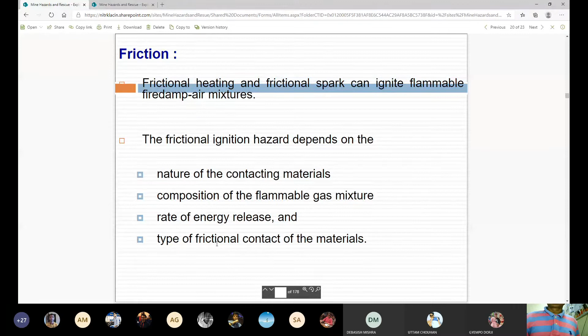So the frictional ignition hazard depends on four factors: the nature of contacting materials, which material is contacted with which material; the composition of the flammable gas mixture, if in your mind there is a methane air mixture; the rate of energy release; and the type of frictional contact of the material. What type of materials are contacted for friction? So let us see what are the different types of materials which can create flame because of the friction.